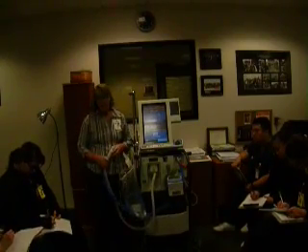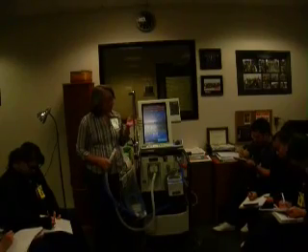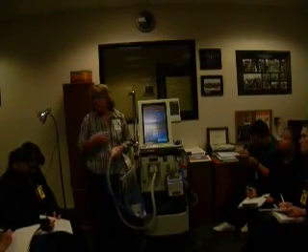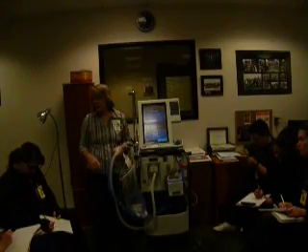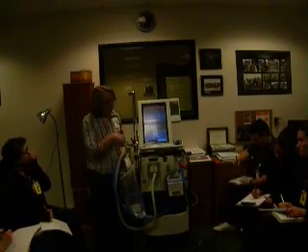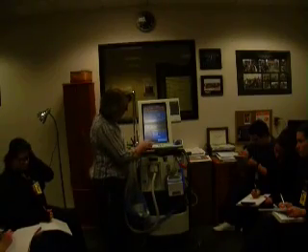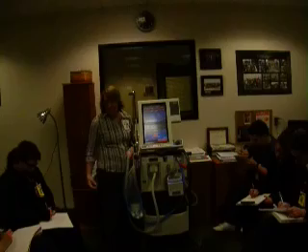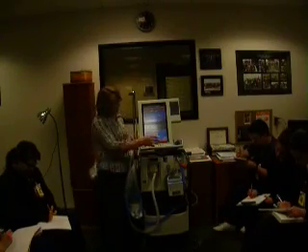We don't use that, no one does, but you can put in the ideal body weight, and then the ventilator will set settings that it thinks are appropriate for that size ideal body weight. So I just typically bypass it, but you do have to touch it to get to the next spot. You have to at least touch ideal body weight, and then hit continue.